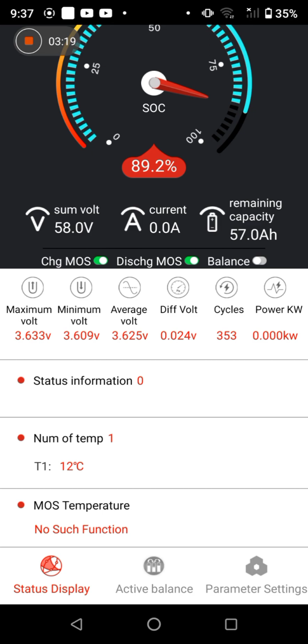So I reckon, rough maths, in the space of about 3 and a quarter hours I've gone from a maximum cell over-voltage cutout of 3.6, with one cell down at 3.33, so well up there in the hundreds of millivolts difference between upper and lower, to being absorbed at 58 volts in the space of 3 hours. I don't see any point in pushing it any higher.